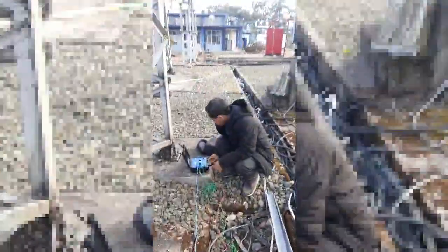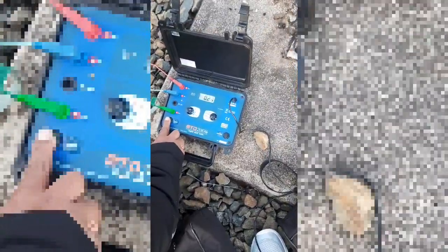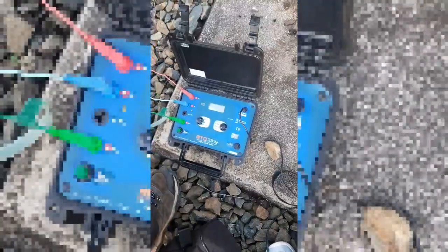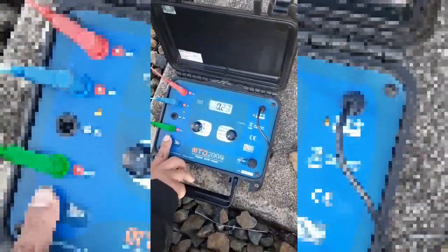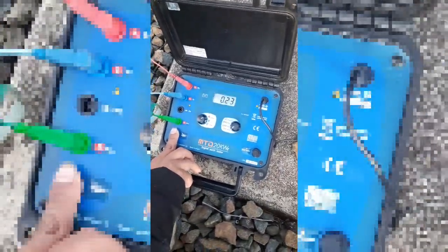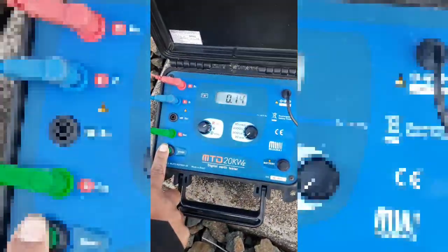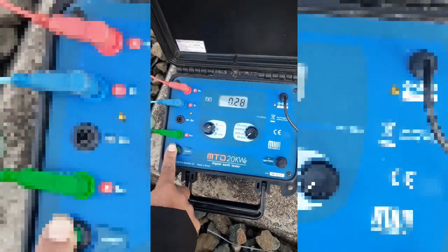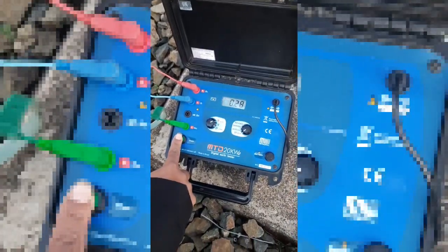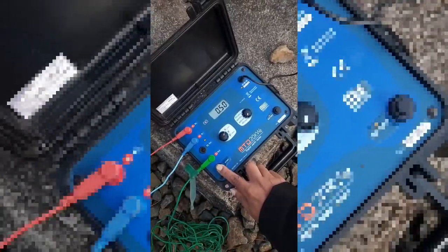Even the Inspectorate of Electricity, when they do checking or want to give you clearance, will ask for these two values, or they will come themselves. This in fact happened with our ICT also, because ICT 3 was under continuous shutdown for more than 6 months, almost a year. After we rectified it and sealed the SF6 gas leakage on the Y phase of the HV side, we asked for clearance, and the RLDC said we had to get clearance from the Inspectorate of Electricity. We applied, and they were asking only these two parameters: the IR value of the breaker, and the earth resistance. If earth resistance is more than 10, they may not give you clearance.